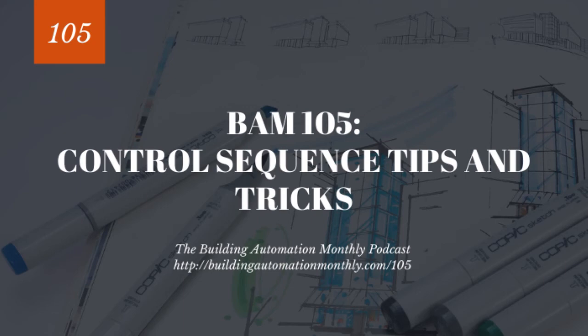So the third scenario, once again, understanding systems, was working on a church, and this church was huge. It was, oh my gosh, I want to say 1,000,000 square feet, but I don't think it was. I think it was like 500,000 square feet. It had 22 air handlers, 3 centrifugal chillers, and a decoupled primary secondary loop. And basically what was happening, so with decoupled loops, essentially the primary loop volume is constant and the secondary loop volume varies. A decoupler is basically a bridge pipe that connects the secondary and the primary loop.